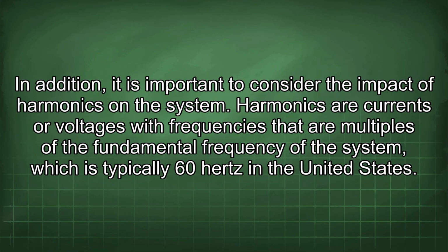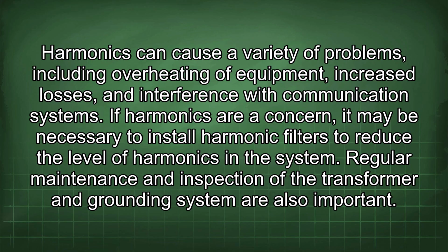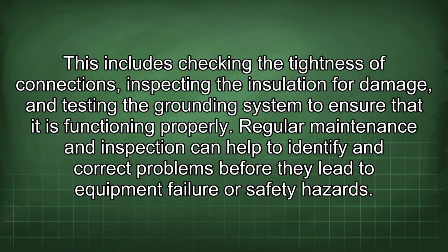In addition, it is important to consider the impact of harmonics on the system. Harmonics are currents or voltages with frequencies that are multiples of the fundamental frequency of the system, which is typically 60 Hz in the United States. Harmonics can cause a variety of problems, including overheating of equipment, increased losses, and interference with communication systems. If harmonics are a concern, it may be necessary to install harmonic filters to reduce the level of harmonics in the system. Regular maintenance and inspection of the transformer and grounding system are also important. This includes checking the tightness of connections, inspecting the insulation for damage, and testing the grounding system to ensure that it is functioning properly.